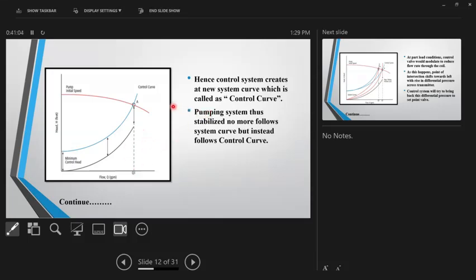So the control system creates a new curve, which is known as a control curve. Now, the pumping system stabilizes and follows no system curve. It follows a control curve. So now the pump logic controller, or PLC, whatever you may like to call it, actually follows this curve, which is known as a control curve. This is clear?